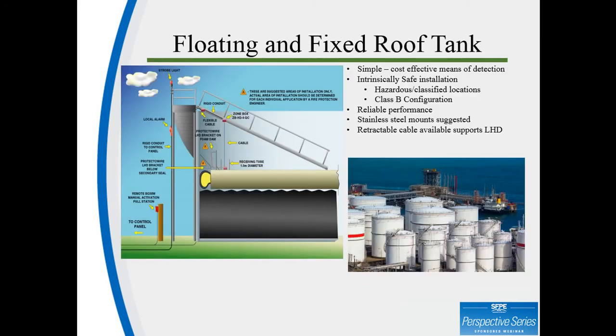Fuel and chemical storage is another common application for linear heat detection. Protectowire can be used on open-top floating roof tanks, fixed-top floating roof tanks, and fixed roof tanks. For open-top floating tanks, pictured in the illustration here on the left, the linear heat detector should be placed below the secondary seal, just above the primary seal, as this is most likely where the flammable vapors will collect. This can be difficult to access, however, and if that's the case, the detector should then be placed on the foam dam just outside of the secondary seal.